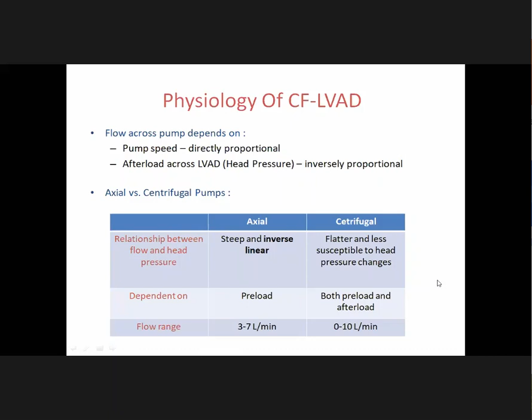In order to overcome these disadvantages, they have designed the centrifugal mode compared to the axial mode, because in axial mode the relationship between the flow and head pressure is steep and inversely related. If the afterload is increased in axial systems, automatically the output will come down, whereas centrifugal flows are less susceptible to head pressure changes. Hence in axial flows the flow coming out of the LVAD depends only on the preload, whereas in a centrifugal system it depends on both the preload and afterload.